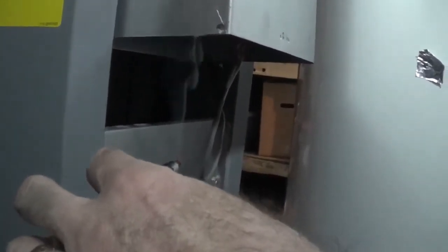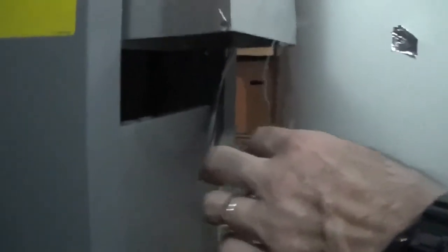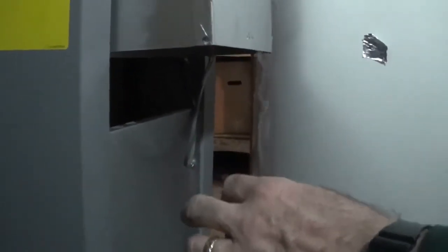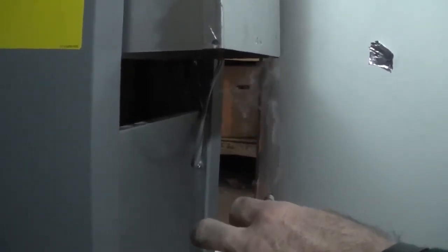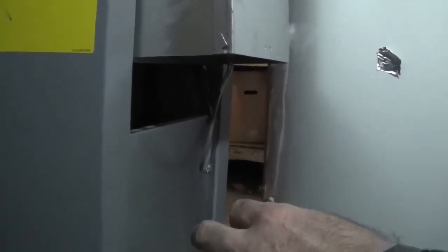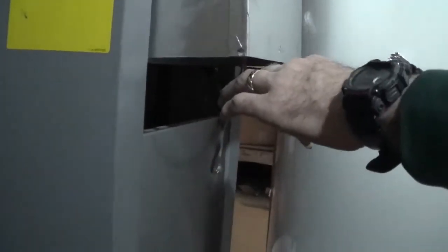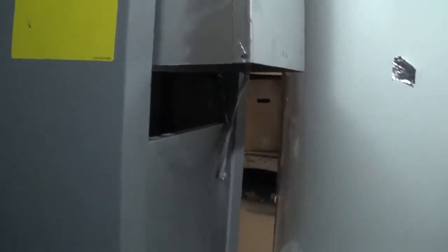So it's been about 60 seconds now, and I'm not ready to say that this passes with flying colors on spillage under natural conditions. As it's billowing out to the side, it's kind of going back and forth. It wants to be getting sucked in. I should be able to hold this pencil maybe 4 inches down and a couple inches out, and I should be able to see that smoke getting sucked in. It's not. And I can feel hot exhaust gases pushing down against my hand. Some people use a mirror to see if the fogginess happens. That is still failing spillage under natural conditions.